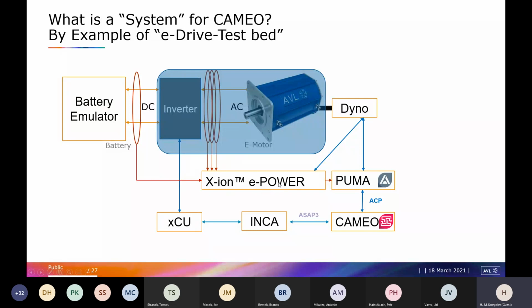So it's the X-ion. So it's at the end nothing else like indication, but with a bit of eDrive features to get the power. And also the dyno - the mechanical power to measure - is not so trivial anymore, because we have torque oscillations, and such a working cycle of an e-motor is comparably fast. If you want a comparison with the torque based on such an e-motor cycle, you need to measure the torque in the same system at megahertz level. This is delivered by the X-ion, and the result at, let's say, kilohertz level is then delivered to Puma.